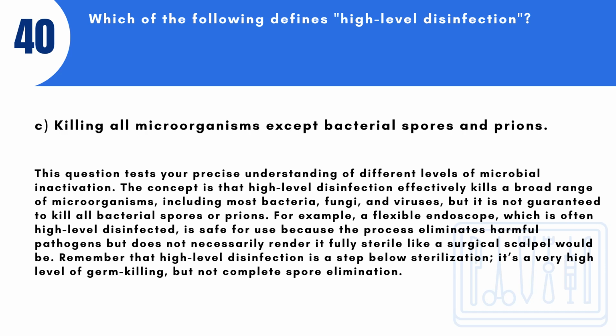This question tests your precise understanding of different levels of microbial inactivation. The concept is that high-level disinfection effectively kills a broad range of microorganisms, including most bacteria, fungi, and viruses, but it is not guaranteed to kill all bacterial spores or prions. For example, a flexible endoscope, which is often high-level disinfected, is safe for use because the process eliminates harmful pathogens but does not necessarily render it fully sterile like a surgical scalpel would be. Remember that high-level disinfection is a step below sterilization. It's a very high level of germ killing, but not complete spore elimination.